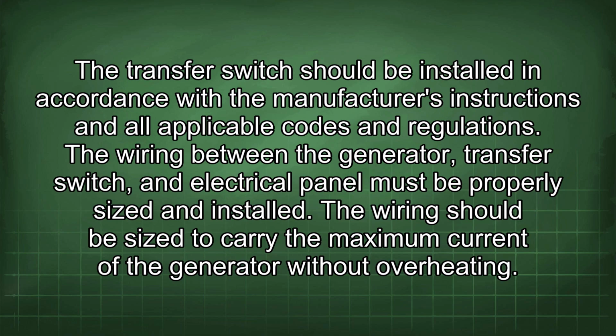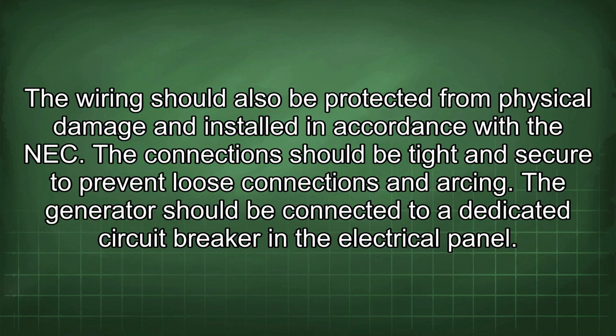The wiring between the generator, transfer switch, and electrical panel must be properly sized and installed. The wiring should be sized to carry the maximum current of the generator without overheating. The wiring should also be protected from physical damage and installed in accordance with the NEC. The connection should be tight and secure to prevent loose connections and arcing.